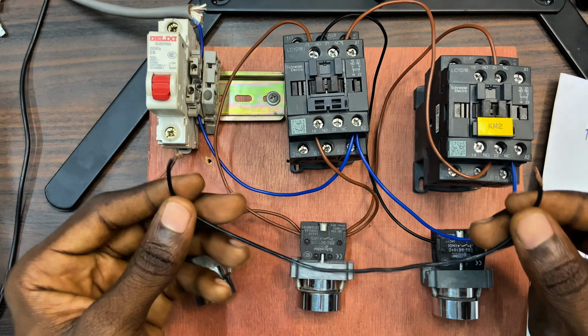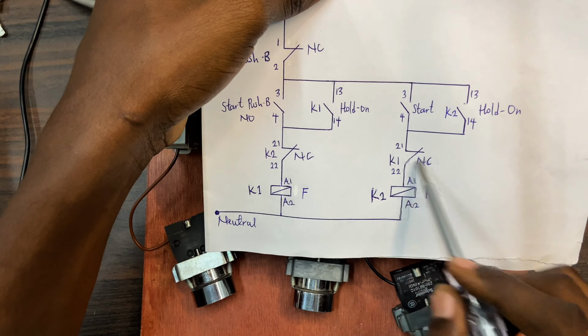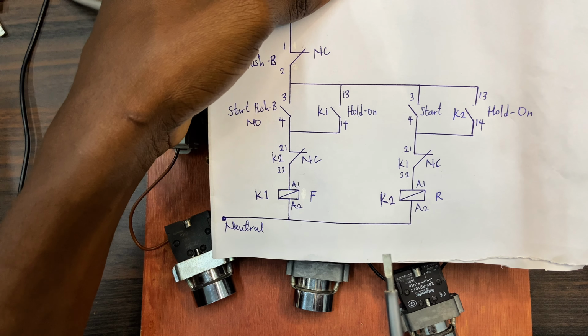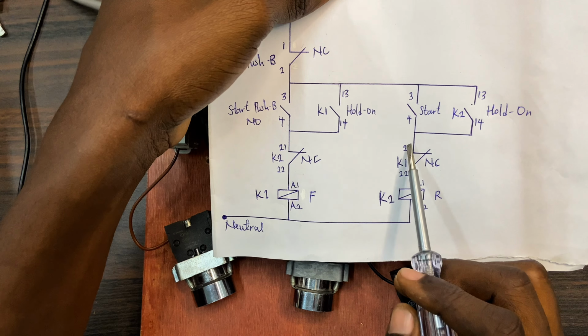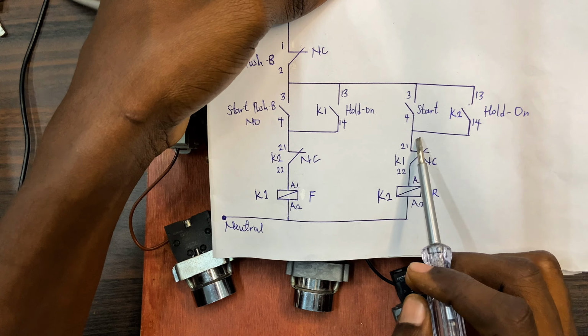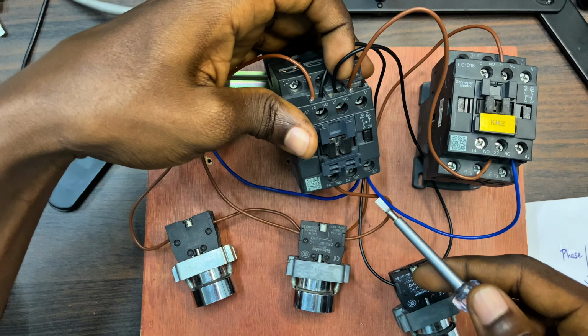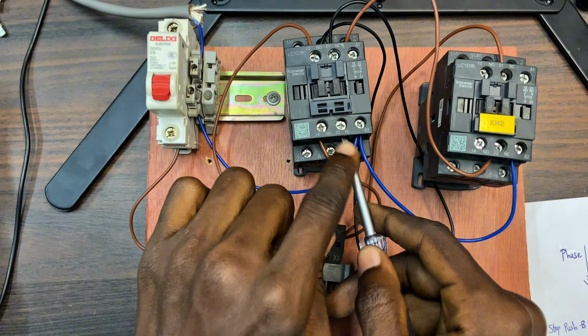So what I have to do is to use this black cable and connect from 4 to 21. Okay. This is the 21. And as I said, the 21 you see at this place can be found on the forward contactor. That is for the interlocking. This is the reverse contactor. We have 21, 22 as normally closed contacts. Okay. And then pick it from 22 to A1.